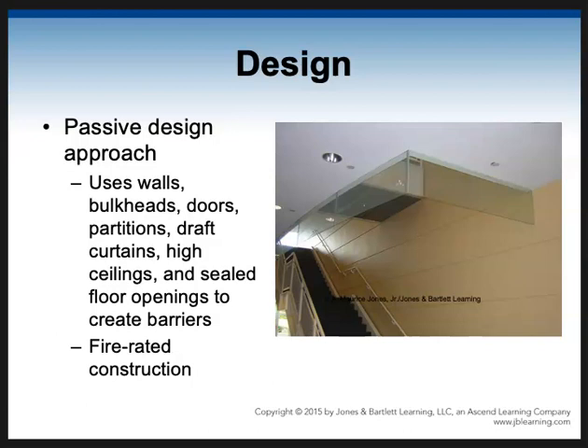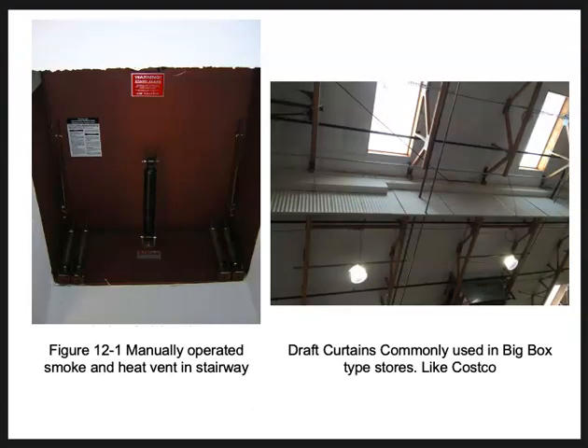So they seal the floor openings to create barriers. They use fire-rated constructions. So here's two examples of passive. Passive is where we just use features as part of the building to keep the smoke compartmentalized or from going from one part to the next. So the picture on the left is a manually operated smoke and heat vent in a stairway. You pop this thing and it allows the smoke out. The draft curtains that are commonly seen, like in the picture on the right, and I took this picture in Costco. So draft curtains are oftentimes just some partition that'll hang down 4 or 5 feet from the ceiling. But I also want you to notice the skylights.